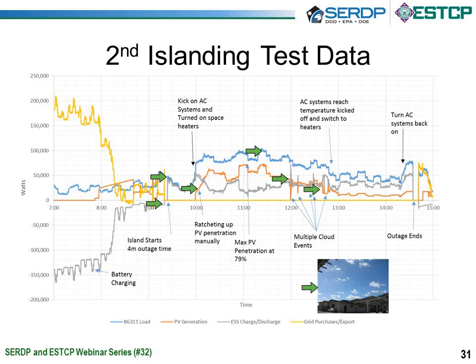In a couple instances, it dropped out 100%. And you can see the response of the battery picking that load back up quite significantly. So we had lots of those events occur throughout the day. We monitored the power quality. The power quality maintained itself.